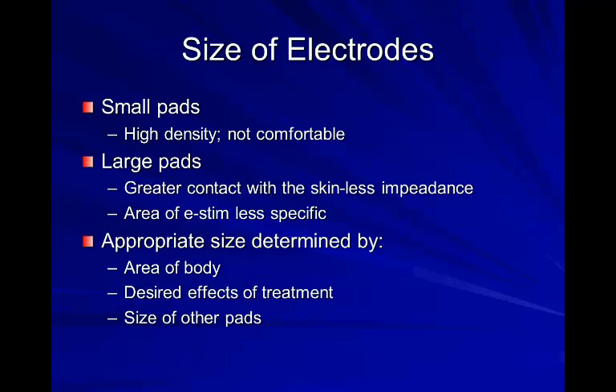Regarding the size of electrodes: the smaller the pads, the higher the current density, which is not very comfortable. The larger the pads, the greater the contact with the skin and the less impedance, though the treatment area becomes less specific. The appropriate size is determined by the area of the body, the desired effects of treatment, and the size of the other pads.